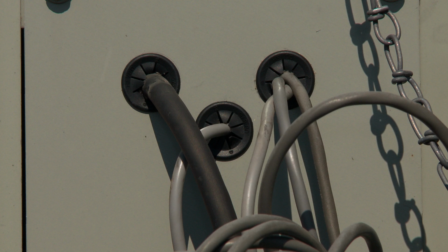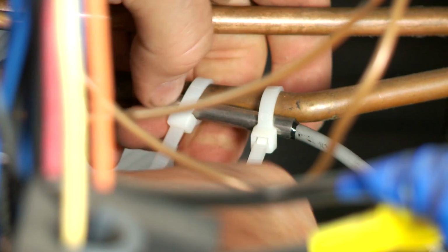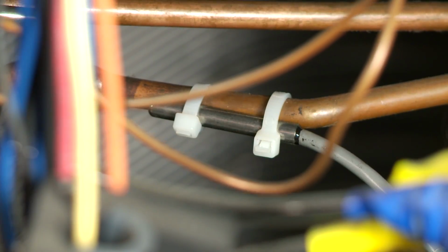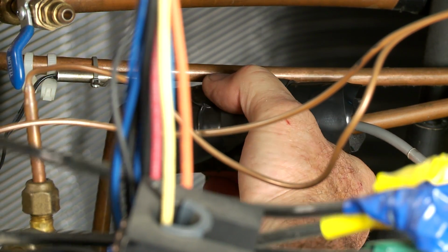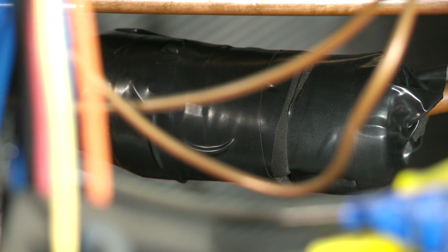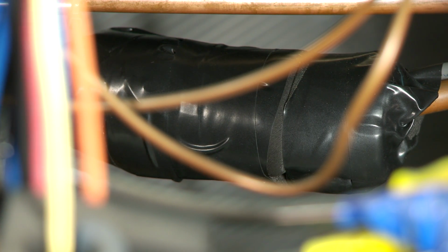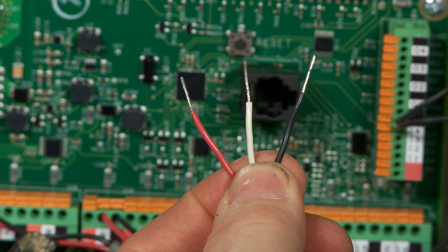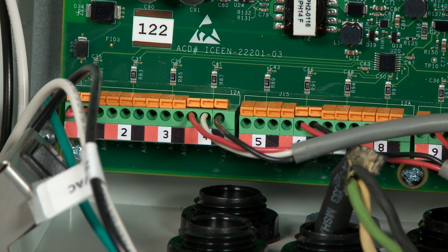If necessary, drill a hole through a cabinet panel to run the transducer wire, and ensure the use of a grommet to prevent the wires from being damaged as they are pulled through to the outside of the unit. Next, attach the liquid line temperature sensor using zip ties to an available section of liquid line inside the unit. Ensure as much surface area of the sensor as possible is in direct contact with the line, fasten securely, wrap with insulation, and then tape until sealed. Connect the bare leads through a cable grip on the controller box and attach to the board.